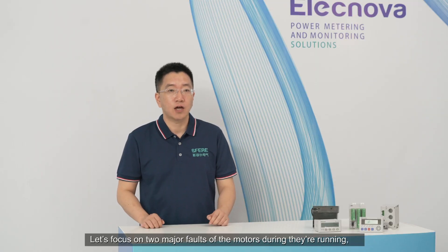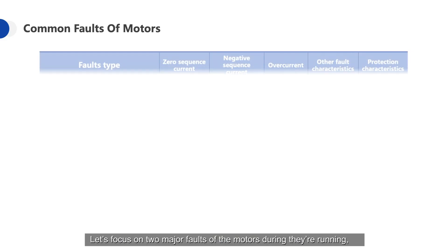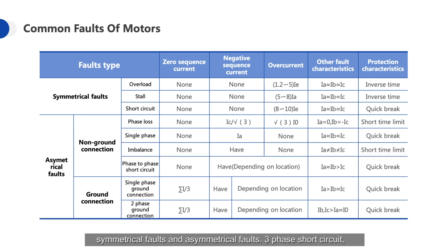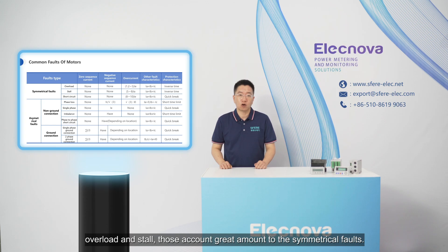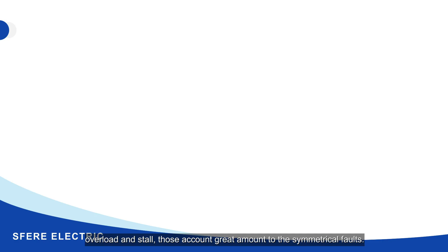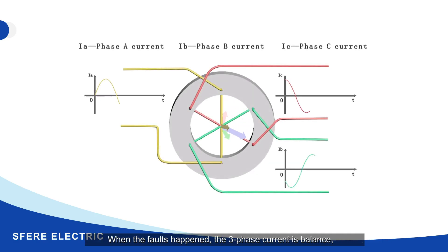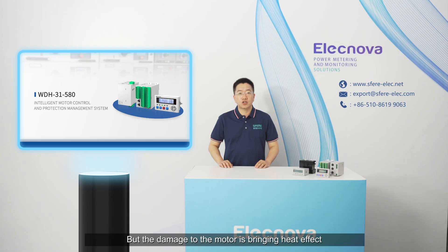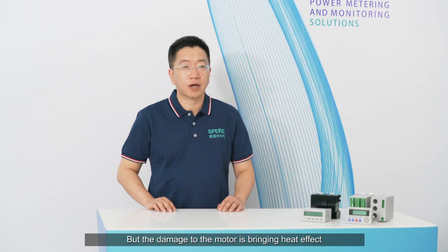Let's focus on two major faults of motors during their running: symmetrical faults and asymmetrical faults. Three-phase short circuit, overload, and stall are among the symmetrical faults. When these faults happen, the three-phase current is balanced, with no negative sequence current and no zero sequence current. The damage to the motor comes from the heat effect caused by the enlargement of the current.